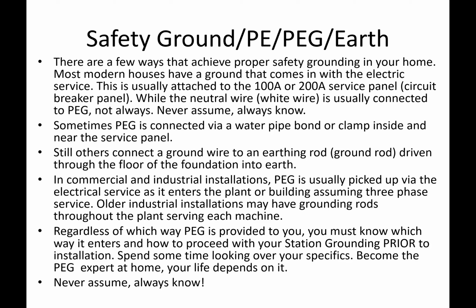Never guess, never assume. Number 2, sometimes protective earth ground is connected via a water pipe bond or clamp inside and near the service panel. This is true for the Emergency Ops Center, or OEM, at Hope Hill Firehouse. Believe it or not, in the utility room, their earth ground is connected to a water pipe, which is serviced by that little room on the outside where the antennas are.